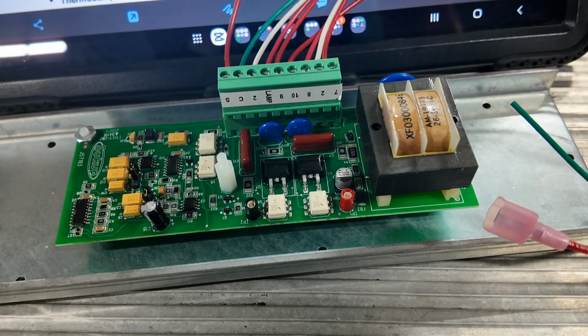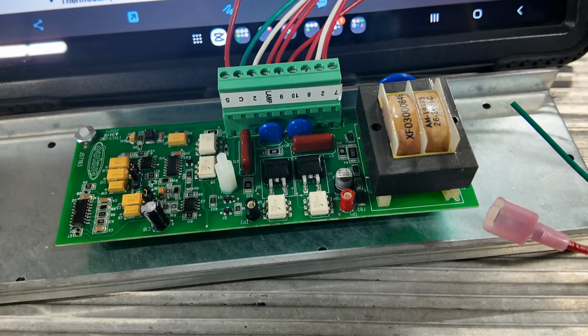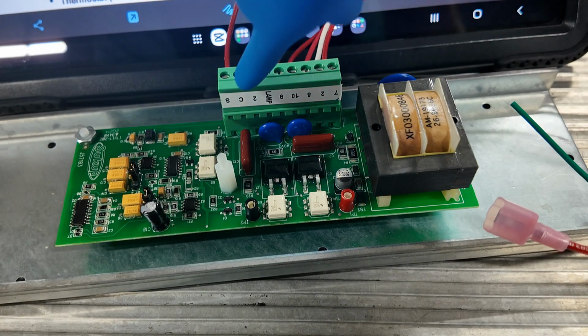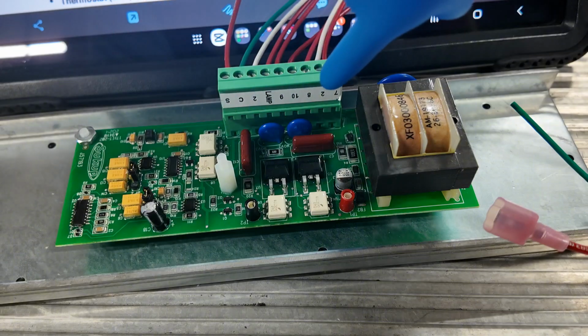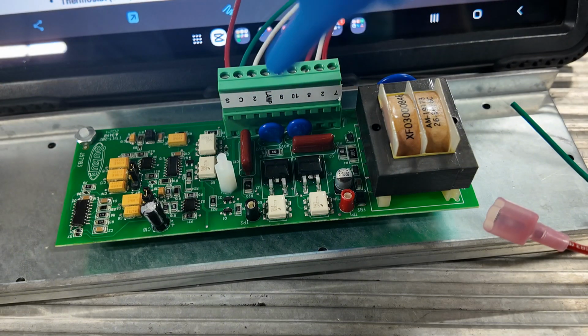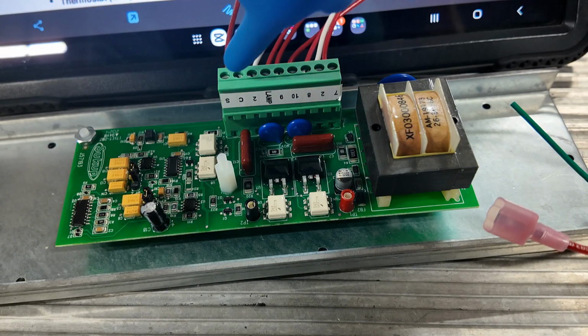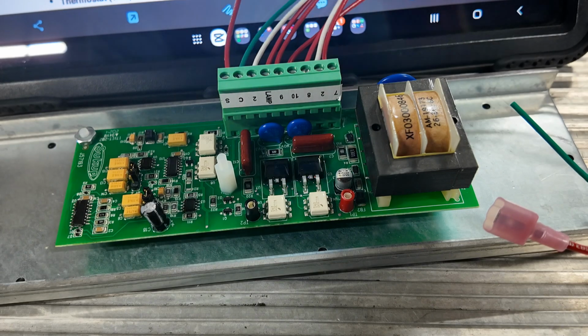These boards are very durable. They're some of the most durable burner boards I have ever worked with. But they occasionally go bad. Sometimes they'll do odd things, but there is only one thing they do, and that is monitor the flame. That's all they do, is monitor the flame. All your other safeties are wired in series ahead of it or connected into a PLC and a dryer.